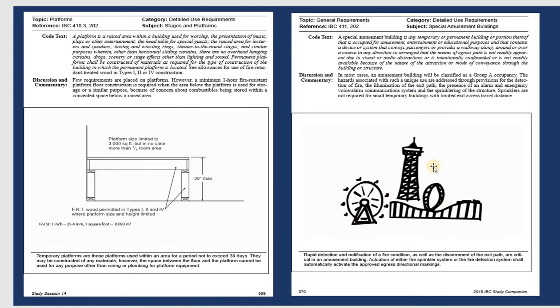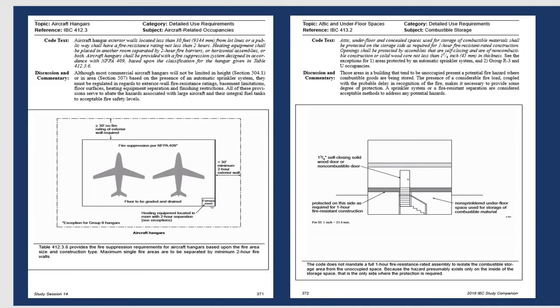So that's why the system for the amusement building, they need to do a sprinkler system, number one for structure. When you use a sprinkler system, the other construction can be lower with the rate. For example, you have 2 hour rate around the wall, but if you use sprinkler inside the building, you can change to 1 hour or 1 hour and a half rate for the wall.